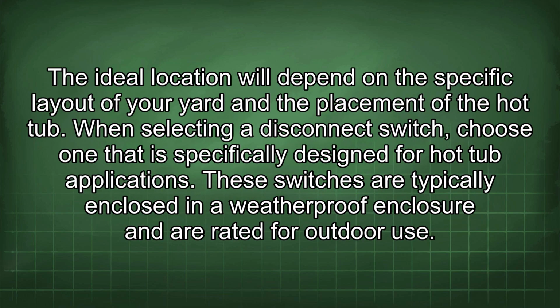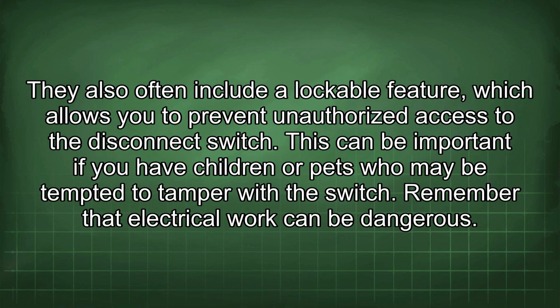The ideal location will depend on the specific layout of your yard and the placement of the hot tub. When selecting a disconnect switch, choose one that is specifically designed for hot tub applications. These switches are typically enclosed in a weatherproof enclosure and are rated for outdoor use. They also often include a lockable feature, which allows you to prevent unauthorized access to the disconnect switch. This can be important if you have children or pets who may be tempted to tamper with the switch.